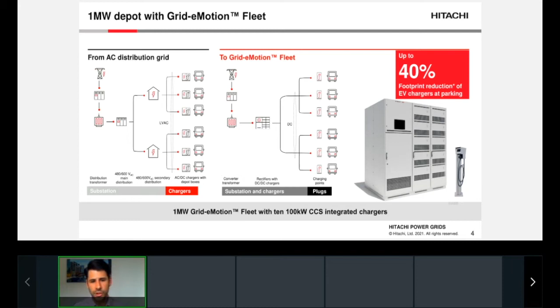Now, what are the benefits of this technology? It's fairly simple: major footprint reduction in the overall system, reaching up to 40% reduction in installation footprint, which is really important. By skipping the whole typical low voltage distribution, we're saving a lot on cabling and required upstream equipment, and reducing the complexity of the system by using proven technology that has been used for tens, if not hundreds, of years to feed one of the first electric vehicles used at scale - trains. We definitely improved the availability.